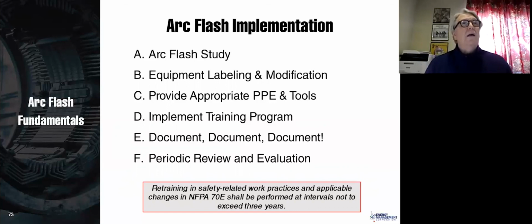So let's say that you are doing an arc flash study. So you have somebody suit up, they open the door so you can take a picture of the breaker and the cables coming into the breaker, and then they step away from that area. Now, a person taking a picture of that can walk within 1 foot because of the likelihood of occurrence and take a picture. But they can only take a picture if nobody is actually doing anything. If they've stepped away from the gear and they're not actually doing anything on the gear.